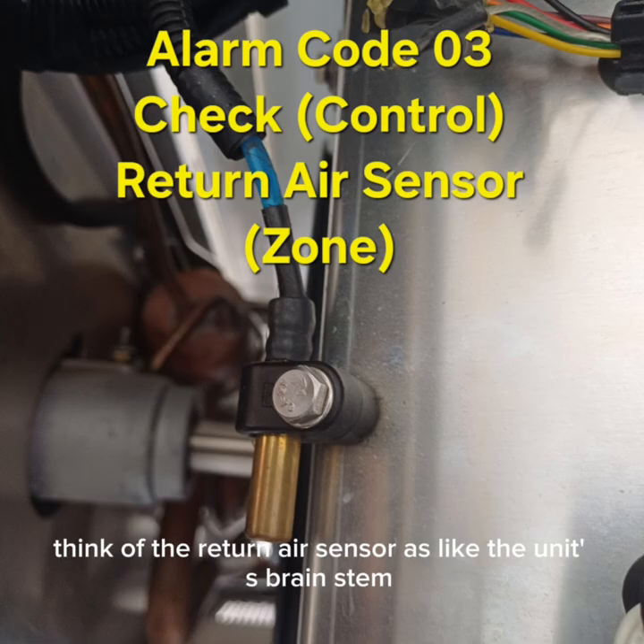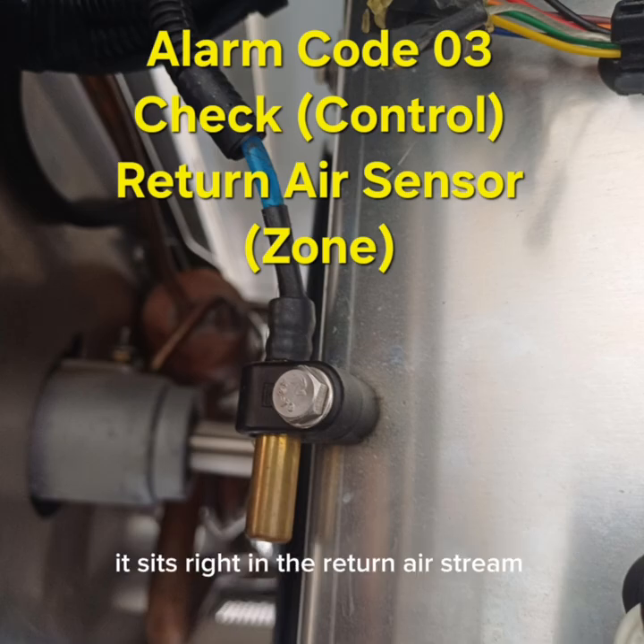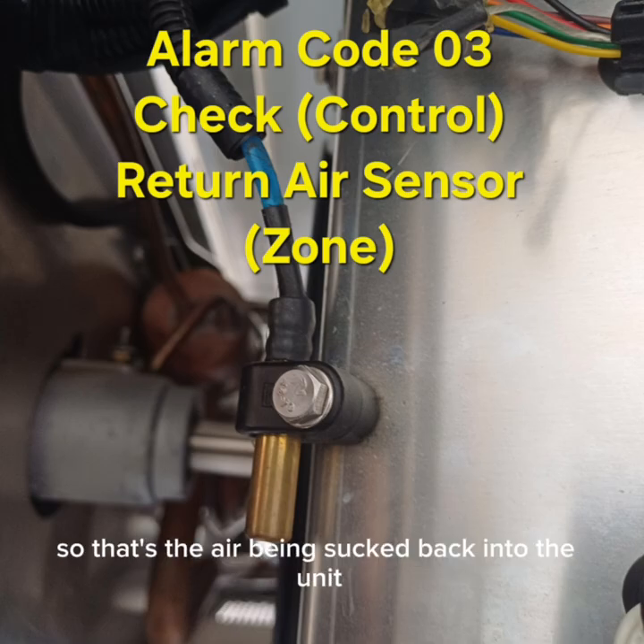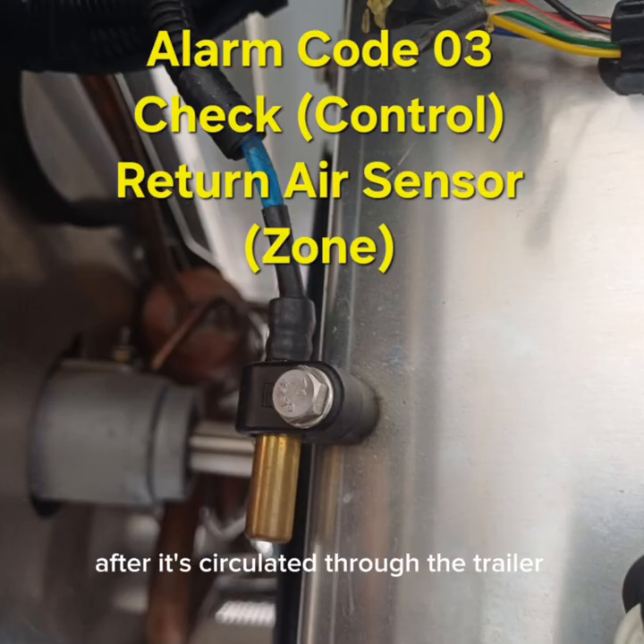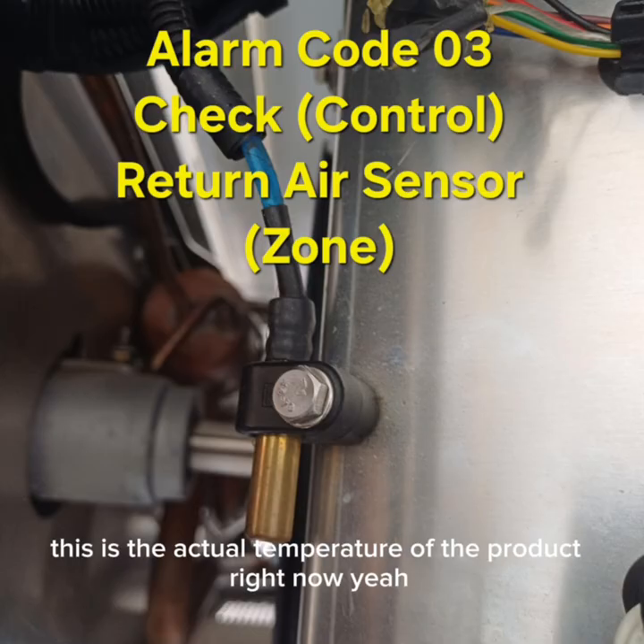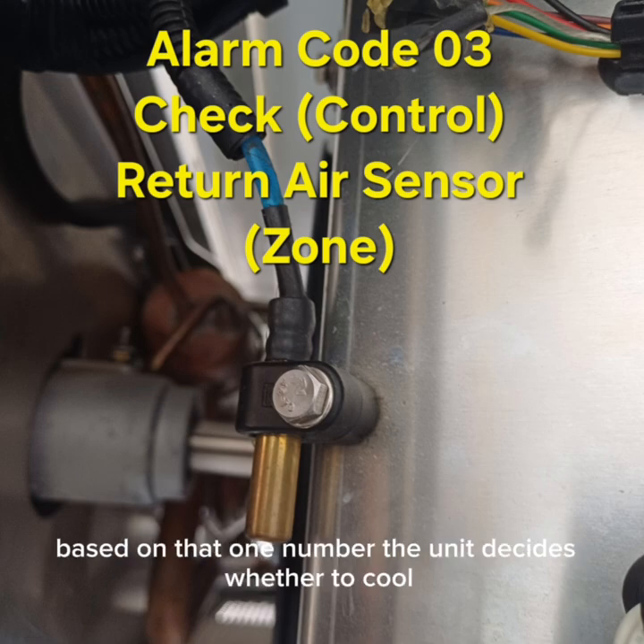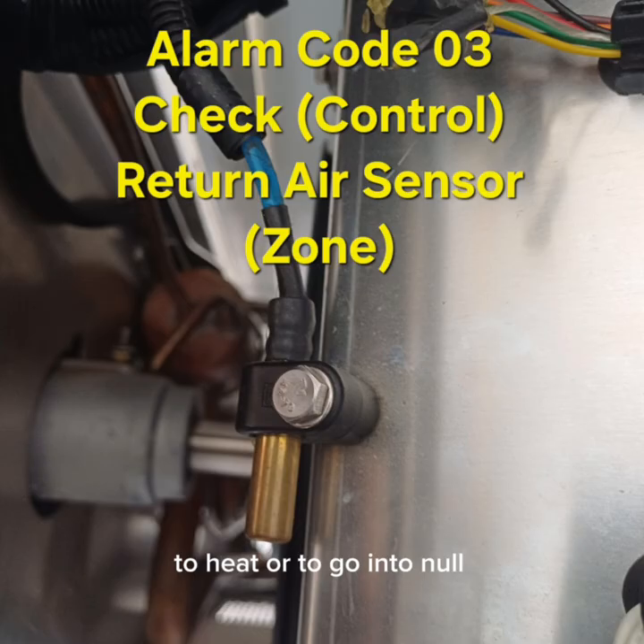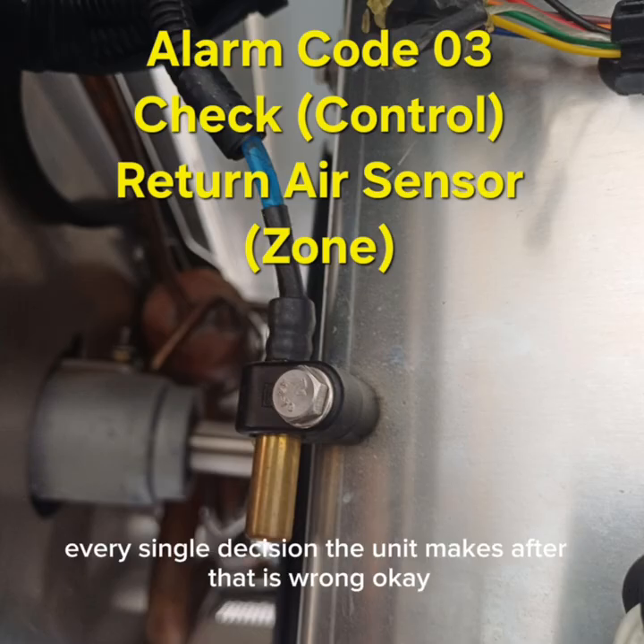Think of the return air sensor as the unit's brainstem. It sits right in the return airstream. So that's the air being sucked back into the unit after it's circulated through the trailer. Exactly. It's telling the computer, this is the actual temperature of the product right now. Based on that one number, the unit decides whether to cool, to heat, or to go into null. If that sensor is wrong, every single decision the unit makes after that is wrong.